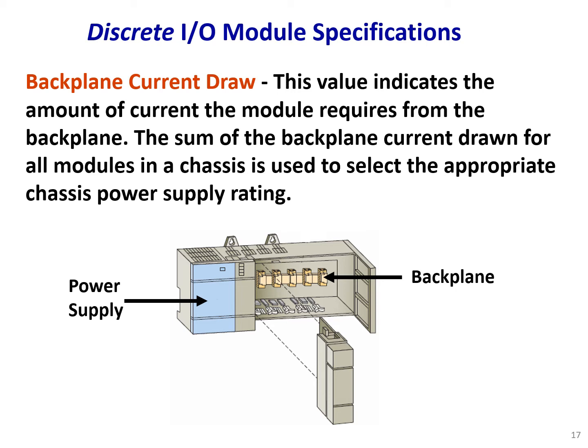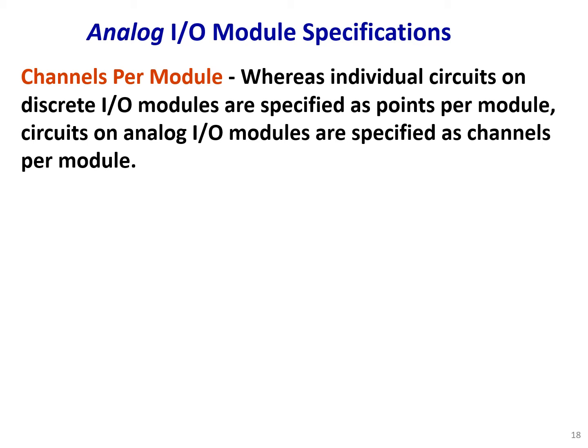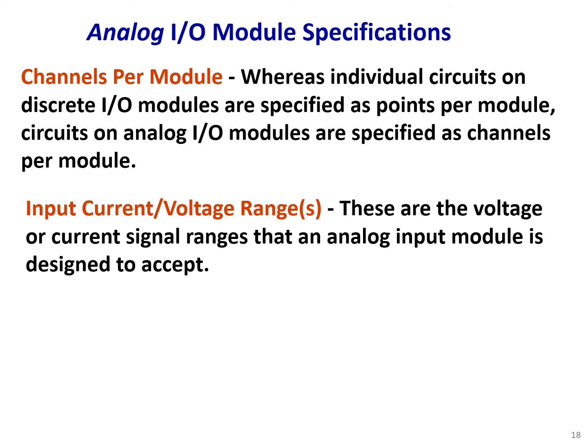Backplane current draw indicates the amount of current the module requires from the backplane. The sum of the backplane current drawn for all modules in the chassis is used to select the appropriate chassis power supply rating. Points is the term used for digital I/O, while channels is used for analog I/O — individual circuits on discrete I/O modules are specified as points per module, and circuits on analog I/O modules are specified as channels per module.